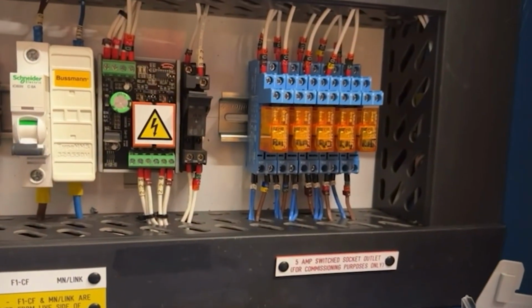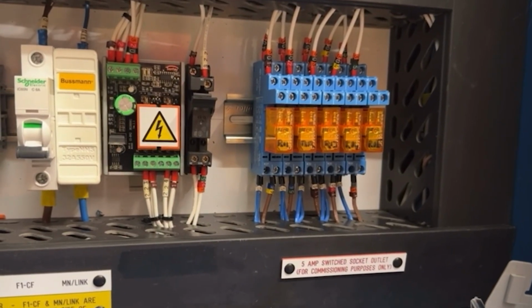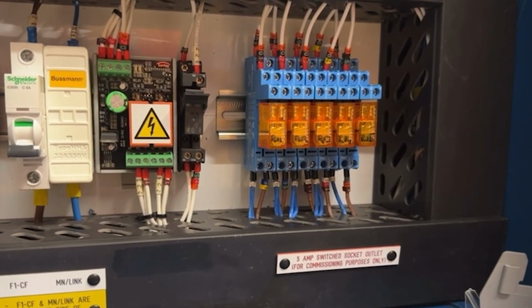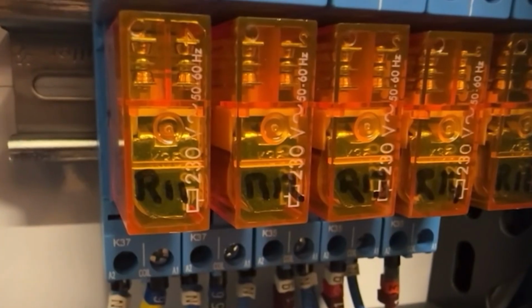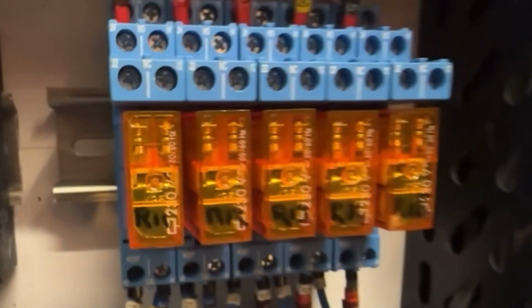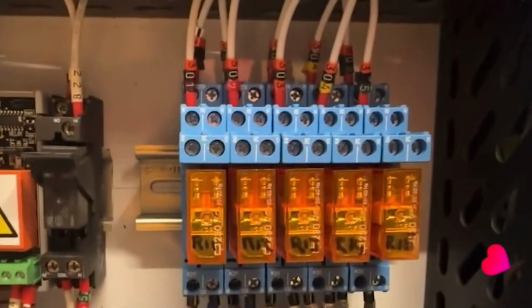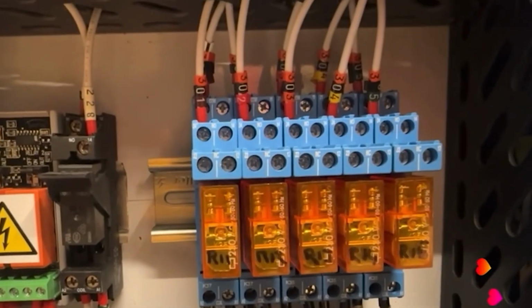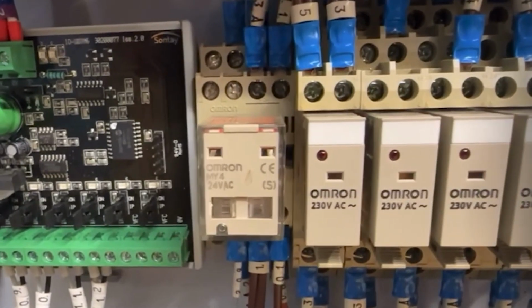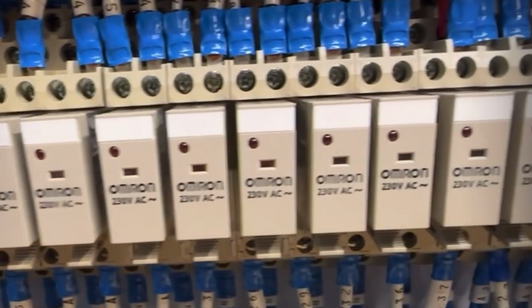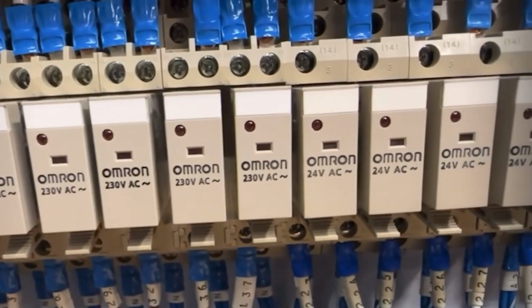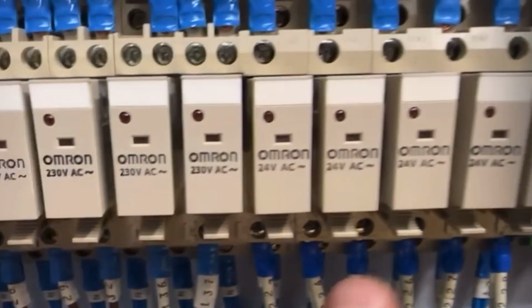So that's what you get for looking. You find out that the socket's not there anymore, but that bank of relays, I wonder what voltage they are. Let's have a look. They are 230 volt relays that have been modded in. That'll be interesting. Maybe we'll take that mod out, maybe we won't, because I suspect it's going to be different to all these relays up here. Well, I can see, oh no, look. They're 230, 230, 230, 230, 230, 230, 230. Then you've got some, oh, there you go, 24 volt AC, 24 volt AC. So you've got some mixture of 24 volt and 230 volt AC stuff.